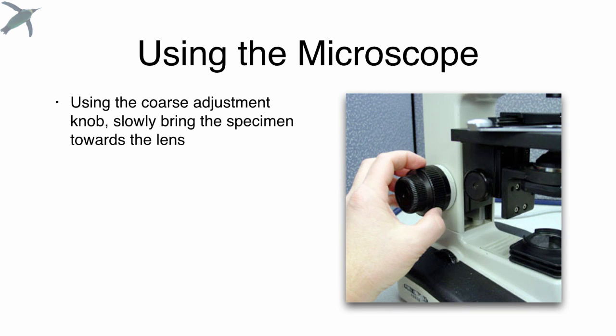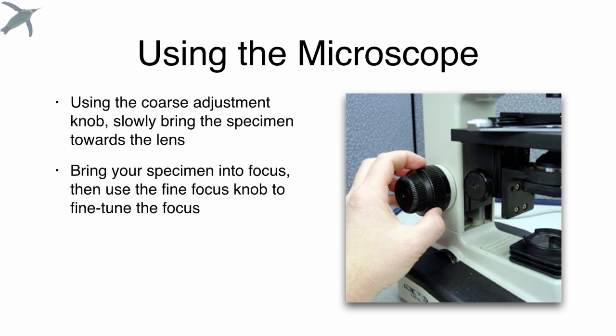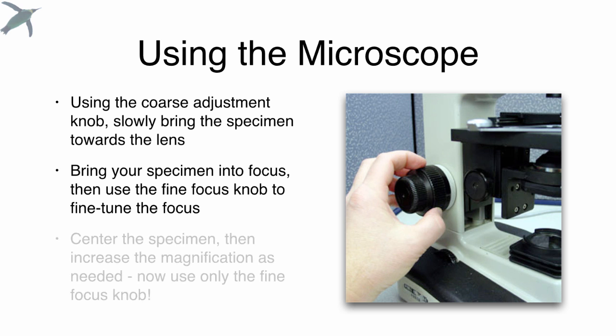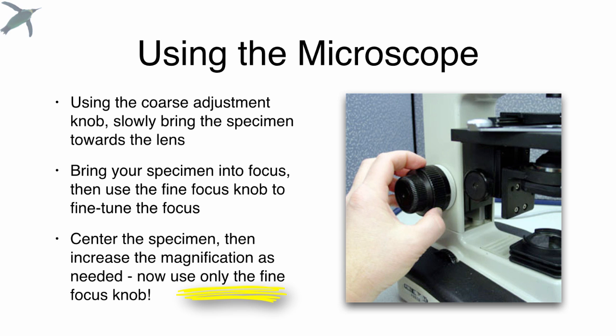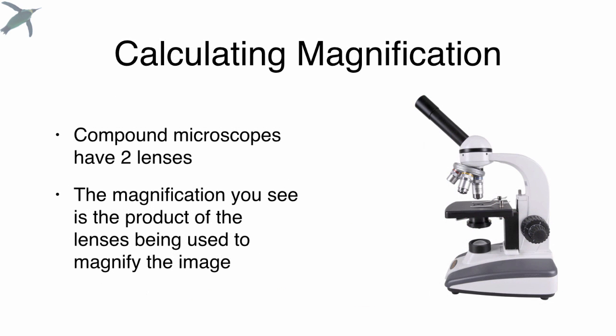The next thing you want to do is use that course adjustment knob to bring the specimen toward the lens. You're either moving the nose piece or moving the stage, but either way you're bringing them together, and you want to bring your specimen into focus. Then you can use the fine focus adjustment to fine tune that focus. You want to center the specimen, and then you can increase the magnification, and now you only want to use those fine focus knobs. The coarse adjustment is for scanning lens work only.